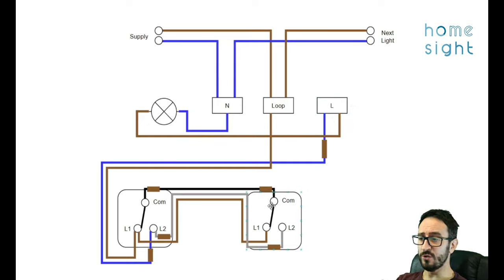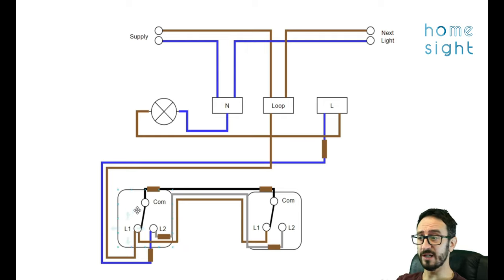Now we've got our two switches down here at the bottom and we've got a loop which is our permanent live coming down into L1 and this blue one here as well but it's got that brown sleeve as well just to show that it could be live. That's our switch live coming down to L2. Now on a switch that's compatible with two-way lighting you will have three terminals or at least three terminals.